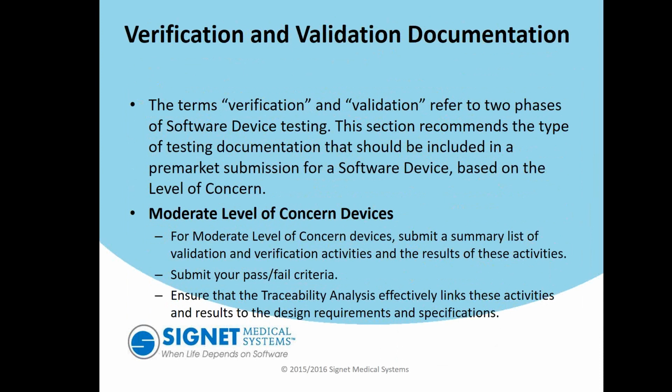So this is another important aspect that the FDA wants to see: all your verification and validation documents, all the pass-fail criteria that has been established. Your documents should pass everything, unless there are bugs outstanding, and we'll talk about those later when we talk about residual bugs.